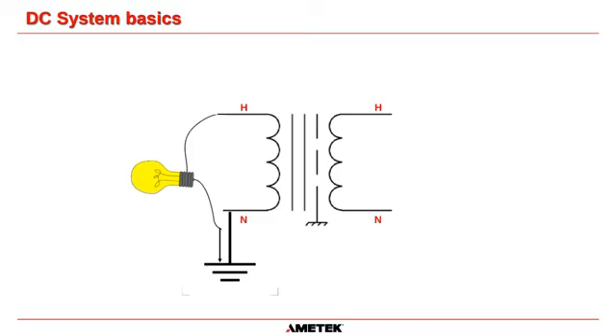So you can see here on this slide, if you connected a lamp between the hot or the live and directly to a ground surface when it's fed from a transformer or the MCC, that will light. Okay, you do have a path because you have this return path back to neutral. It's not the design path, but it is a return path. Okay, hopefully you understand that.